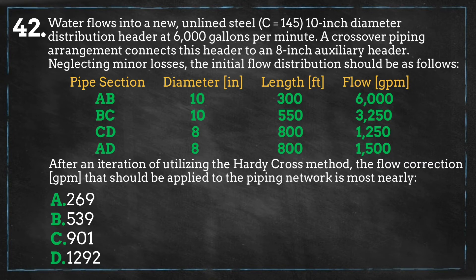The goal of this method is to find the head loss of each pipe in the system, ultimately calculating the total head loss in the distribution system, finding the change in flow created by that head loss across the system, and then applying that change to the various elements in the system — repeating all three steps until the flow corrections bring the system into a range of acceptance.